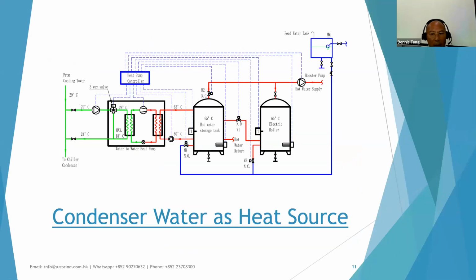Other than using the air conditioning plant to absorb the heat, there is also an opportunity to use the condenser water, that is the cooling tower water, to absorb the heat for the hot water system. This is another method to reduce the waste heat emission to our ambient environment.